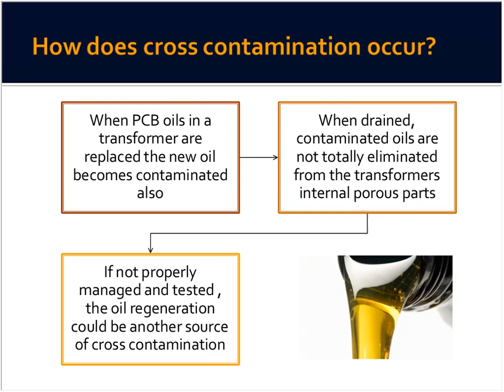Another form is if you have equipment that you use in maintenance tasks, such as hydraulic pumps, hoses, drums, tools, or valves, that you do not isolate and keep away from other maintenance operations, and they have been used with PCB contaminated oil. The oil that remains inside of these valves and inside of the drums will be contaminated again, and will contaminate the clean oil if we use this equipment with clean mineral oil. So we must remember that a small volume of PCB contaminated oil is enough to contaminate large volumes of mineral oil to concentrations above 50 parts per million.